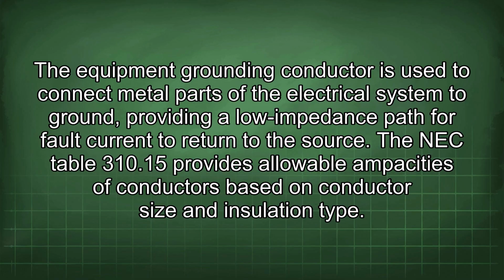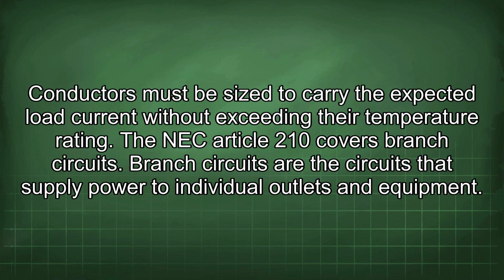The NEC Table 310.15 provides allowable ampacities of conductors based on conductor size and insulation type. Conductors must be sized to carry the expected load current without exceeding their temperature rating. The NEC Article 210 covers branch circuits. Branch circuits are the circuits that supply power to individual outlets and equipment.